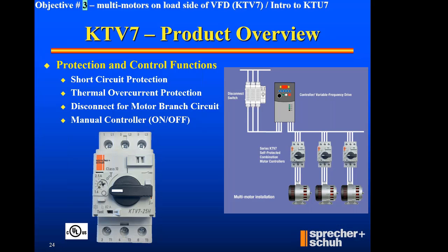Go right ahead. A quick question here. There was a question on how do you set the overload for that? Good question. Visually, I've got a picture of the KTV7 on the screen. To the left of the black rotary knob is indeed a FLA dial, in which you're taking a screwdriver tip and merely dialing in the actual FLA of the motor nameplate. There is no calculation necessary by the user. The thermal overload protection integrated into the unit is already factory calibrated at 120% to go into a time curve once it sees an overcurrent. So just to reiterate, there's no calculation necessary. You're merely going to read the motor nameplate FLA value and dial it in using that dial to the left of the rotary knob. So that's the overload question.